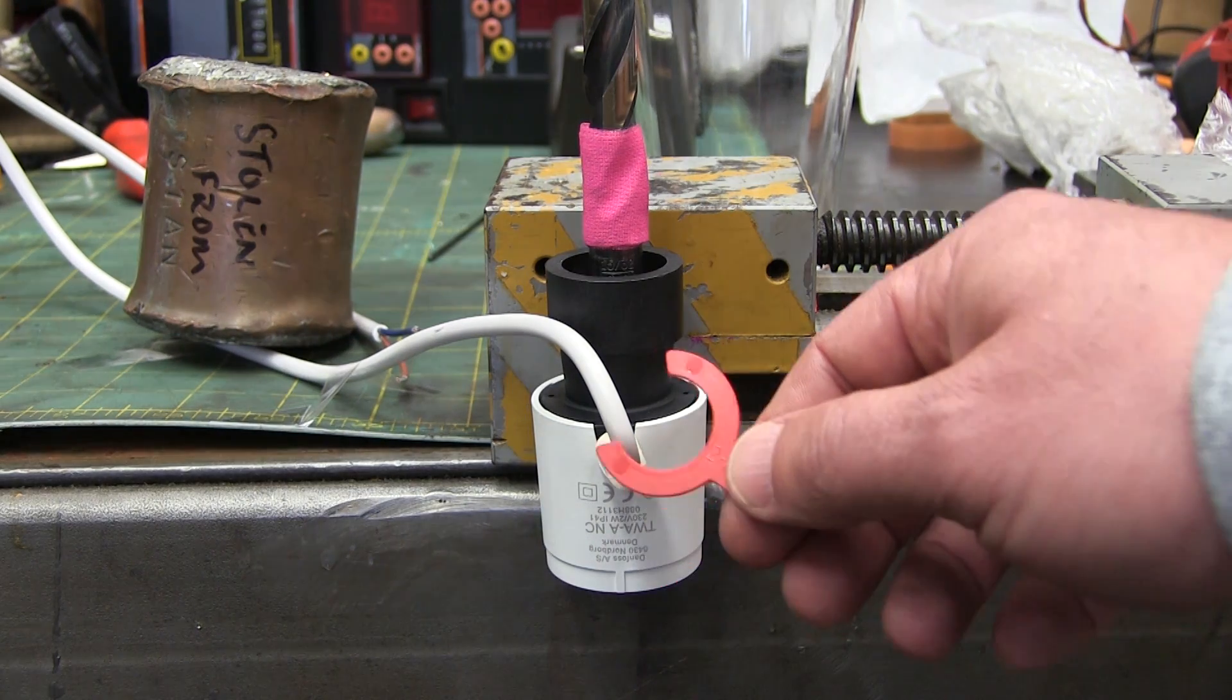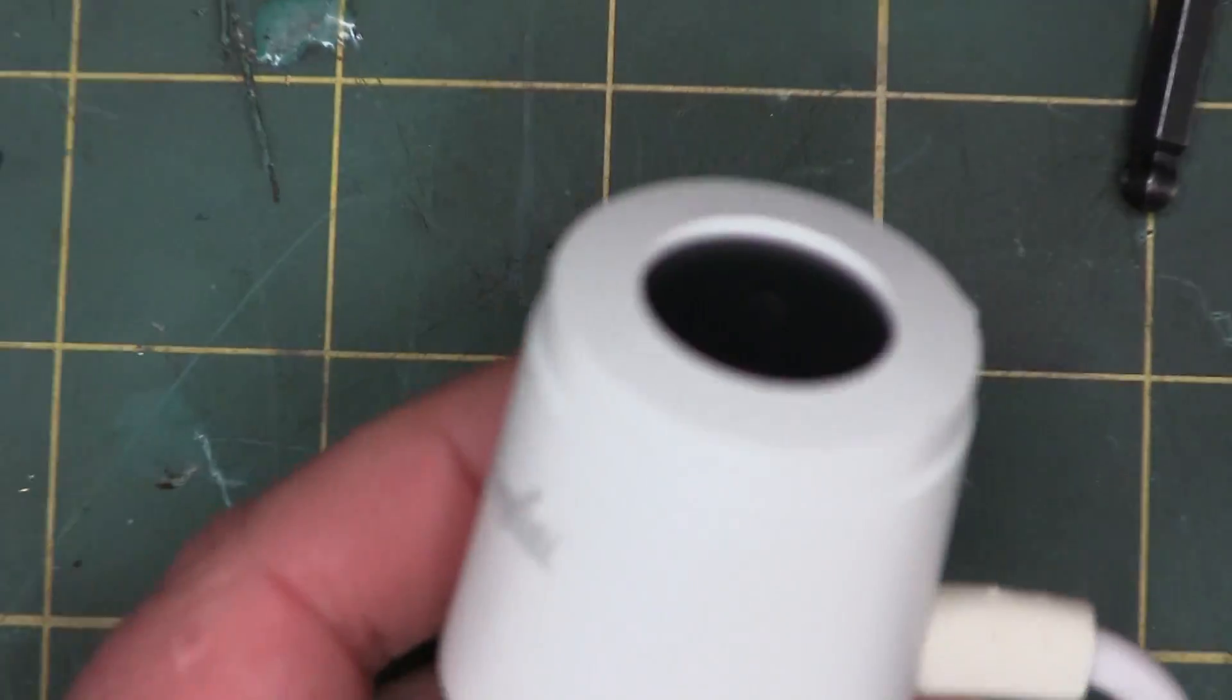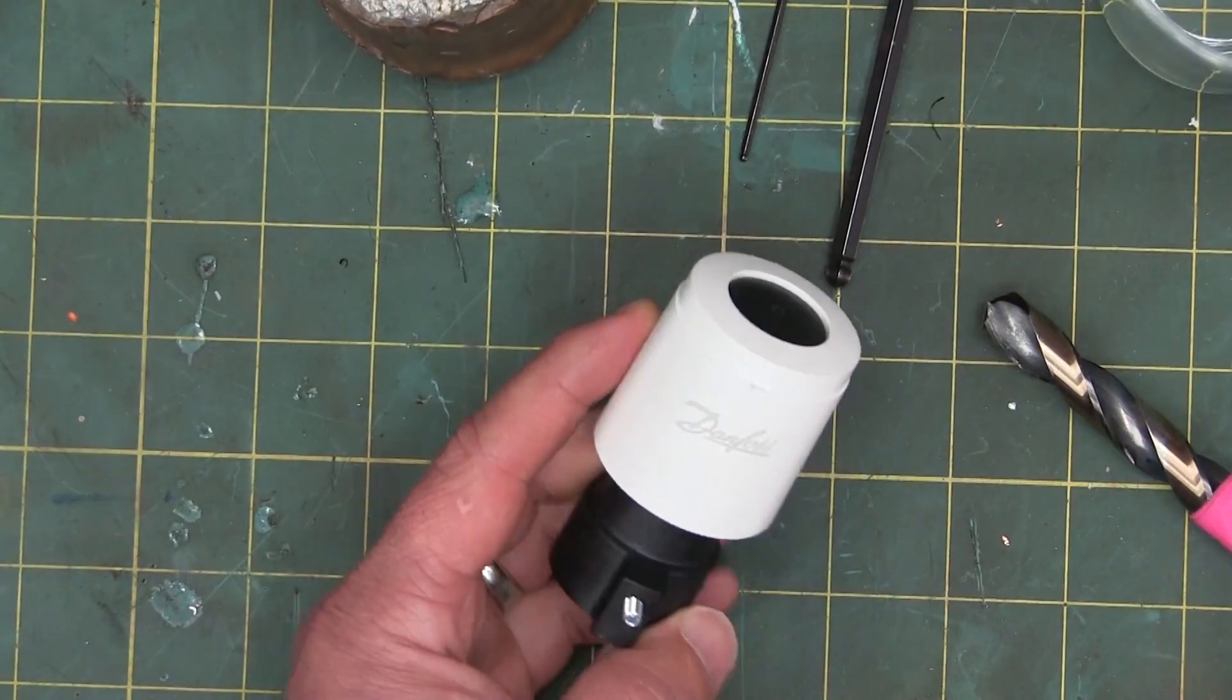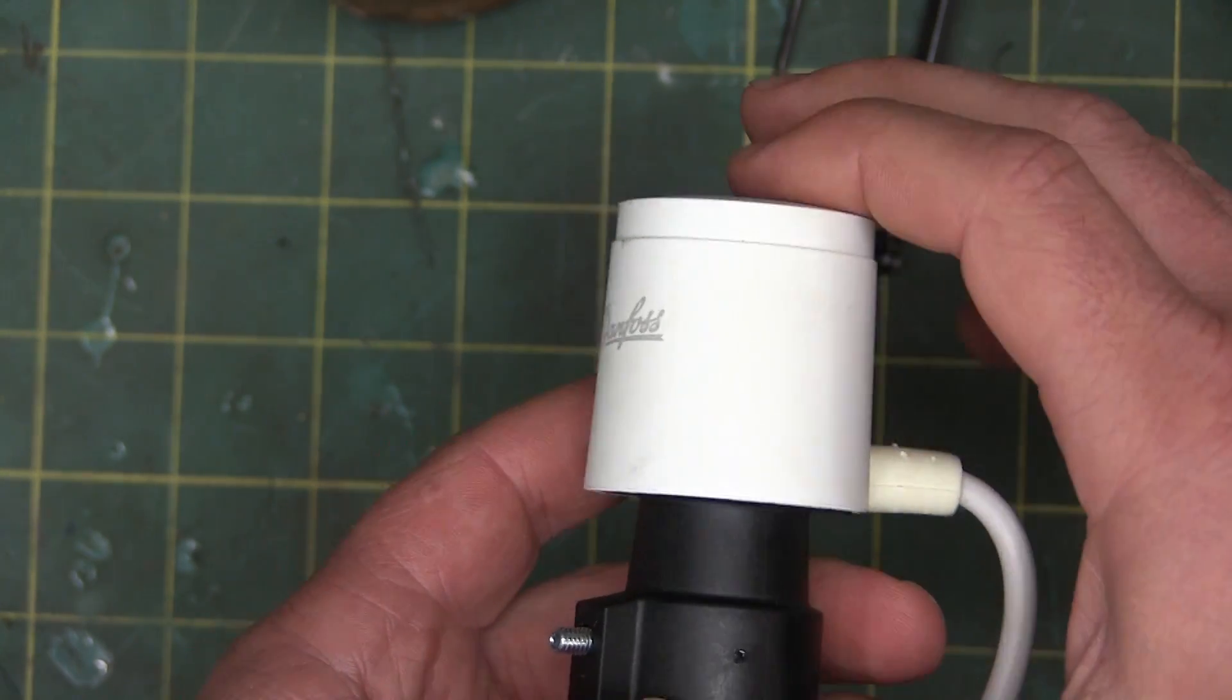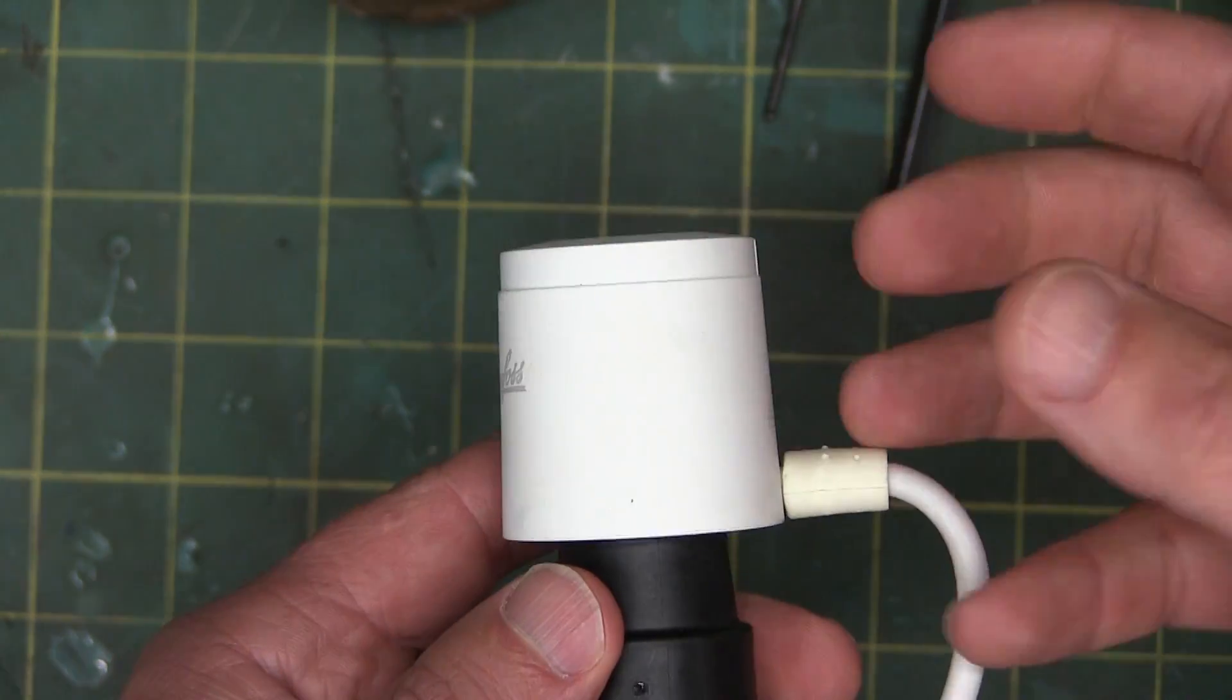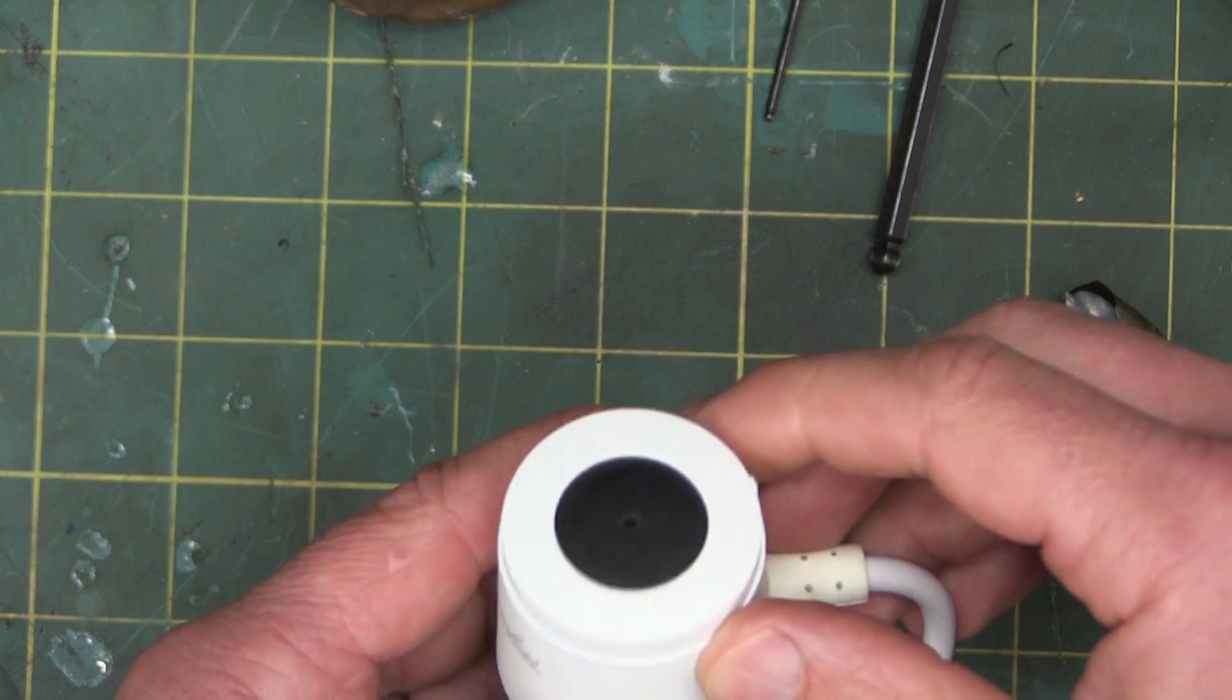I trust we can all agree to never speak of this again. All right, that's the normal position. That is the retracted position, this is a normally closed position, and then when we energize it, heats up the paraffin, changes phase, it goes from solid to liquid, expands, that puts out a hell of a lot of force and this little teat pops out.